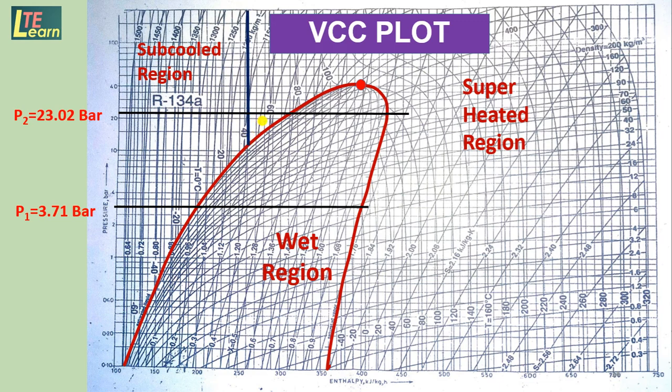condensation temperature, condenser outlet temperature, which was about 41 degrees Celsius. So we get here intersection of this vertical temperature line to the saturated liquid line at 41 degrees Celsius. This is one point we get. Similarly, here this is a temperature line. Here we take temperature after evaporator, that is about 16 degrees Celsius.